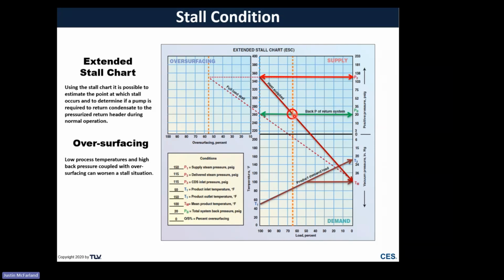And just to briefly explain what's going on here, we've got pressure on the right axis here. We've got our load percent on the bottom x-axis, so you can think of that as heat demand. And then corresponding with the y-axis on the right, we've got this y-axis here in the middle. That's the saturated steam temperature corresponding to those pressures. So without going into too much detail, what this is showing is that with a fixed back pressure, we have estimated steam pressure inside the coils from full load at 100%. Pressure is dropping all the way down to 0%. So we can see that right where these lines cross is the stall point.